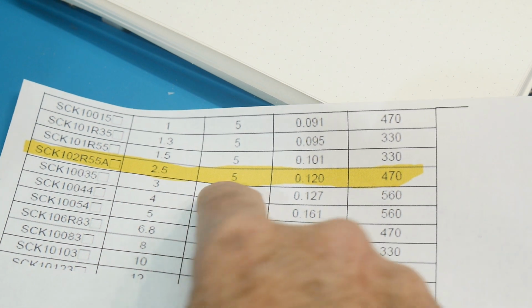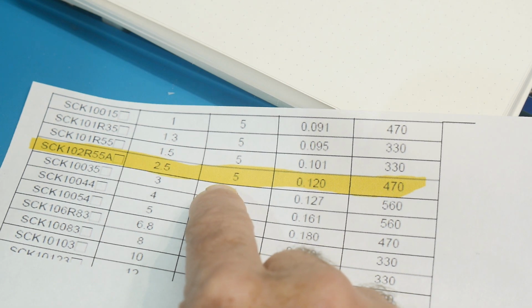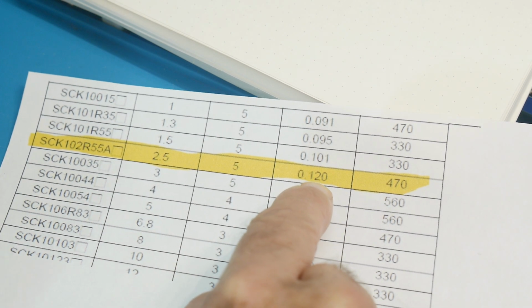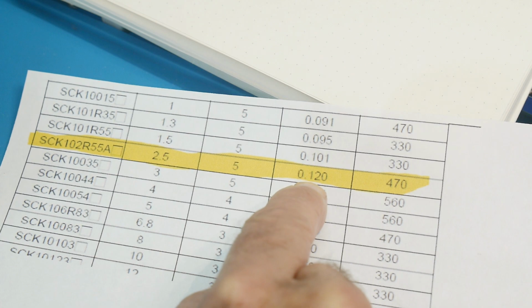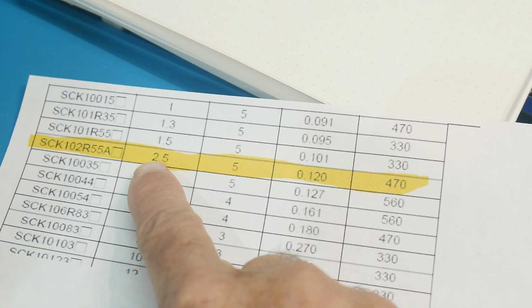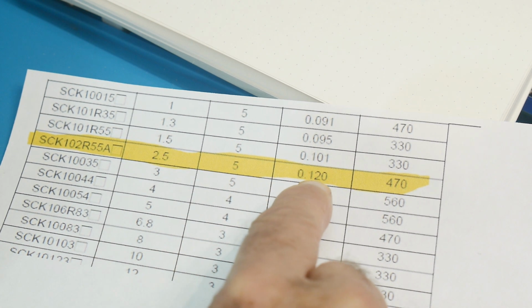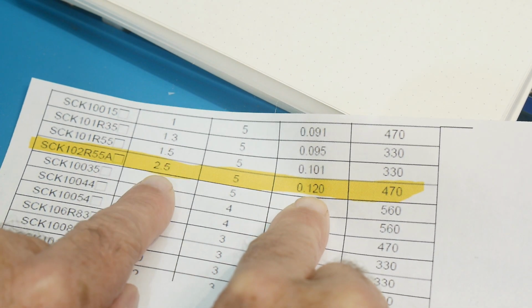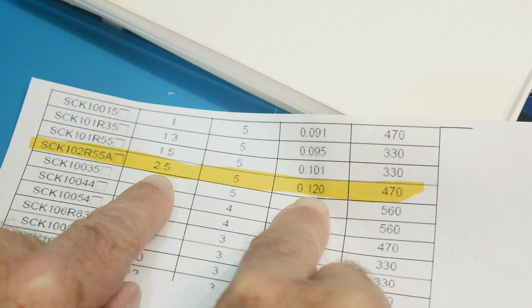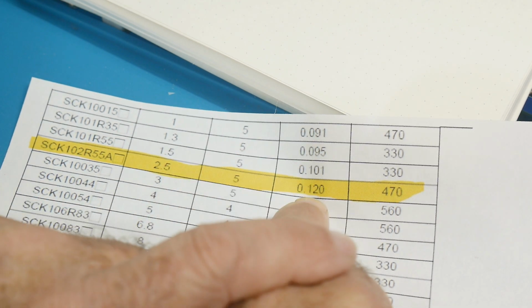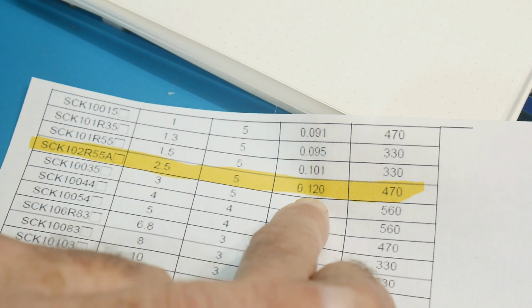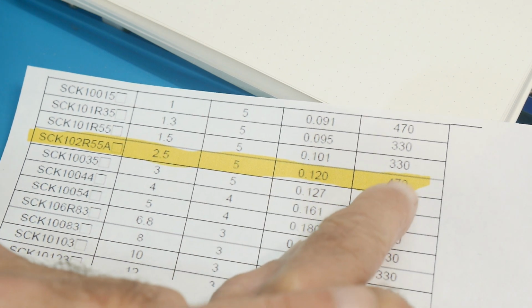It can handle up to 5 amps. This is the ohms when hot, so it starts at 2.5 ohms and drops down to 0.12 ohms. That's what the thermistor does: it starts at high resistivity and lowers itself when it gets hot, and it doesn't take long to get hot. We'll ignore that other number for now, it's a capacitance value for the inrush current and stuff like that.